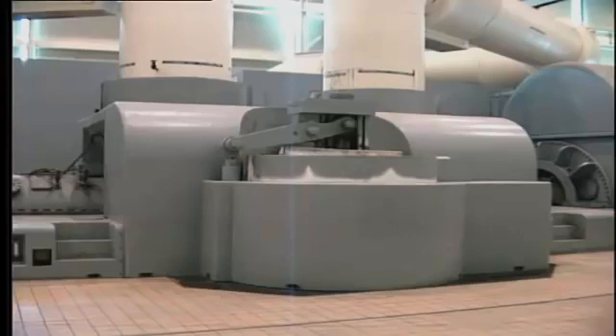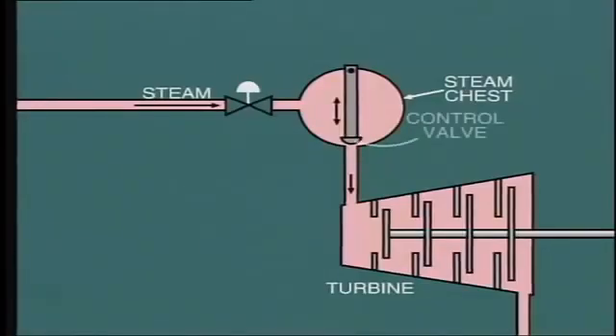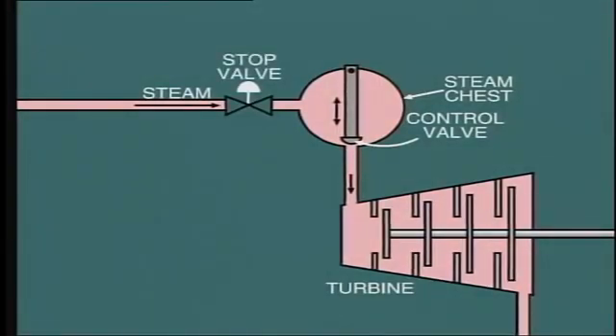One other advantageous factor is the relative ease of controlling the output of the steam turbine. This is achieved simply by adjusting the amount of steam admitted to and flowing through the turbine. Admission valves, also known as control valves, are installed for this purpose. The turbine stop valve is located upstream of the control valves. In case of an emergency, the stop valve closes automatically, cutting off all steam supply to the turbine and bringing the machine to a halt.